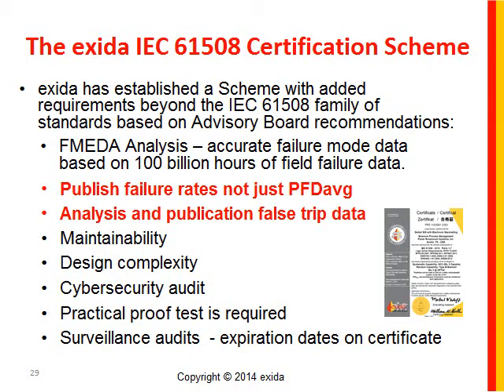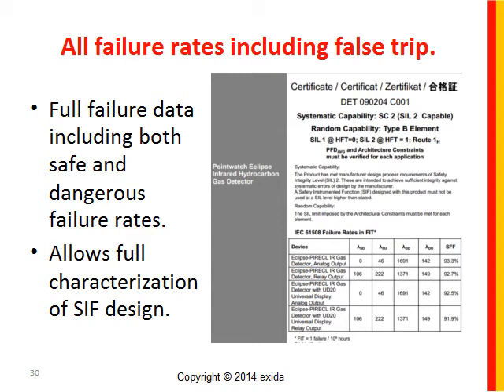In the exida certification scheme, we publish failure rates — not just PFD average — because there are many variables involved in calculating PFD average. We analyze and publish the full false trip data. You can see this on the back page of virtually every single exida certificate; our certificates are available on the exida website. We publish and require that manufacturers publish a full set of failure rate data including both safe and dangerous failure rates, because it allows you the designer to calculate your PFD average based on the variables in your plant, and to calculate the false trip rate, which is awfully important to most of us in the process industries.